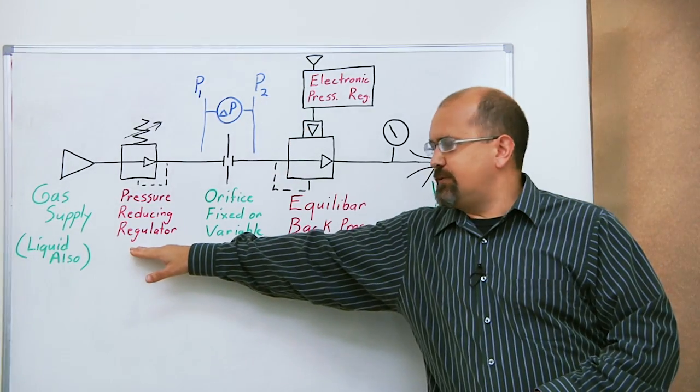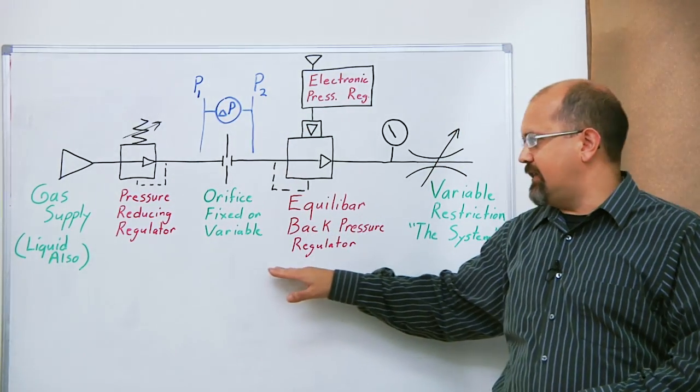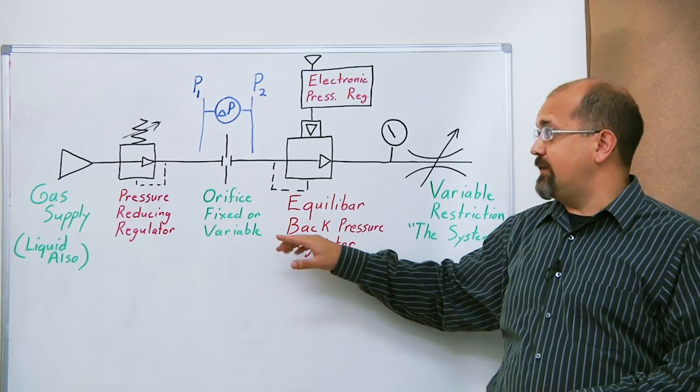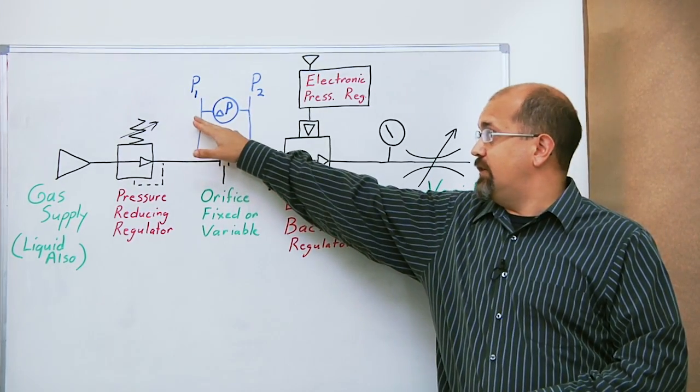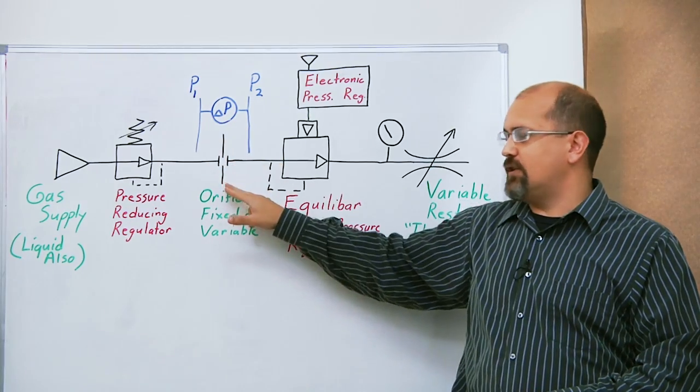Now between the pressure reducing regulator and the back pressure regulator, I've in effect set P1 and P2, which now allows me to control the differential pressure across the orifice.